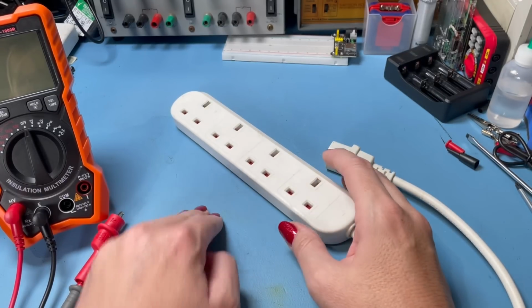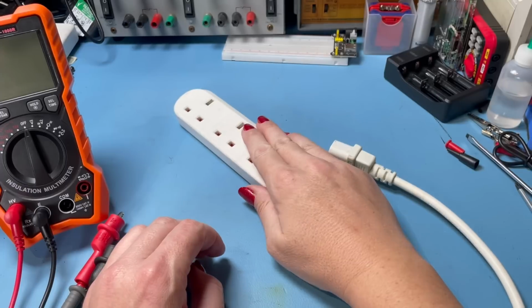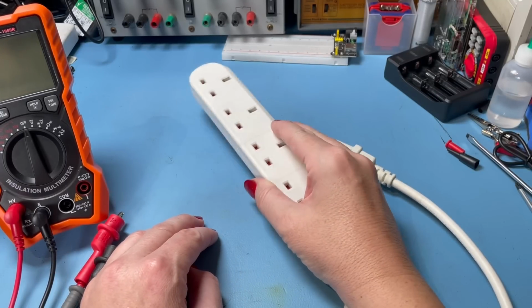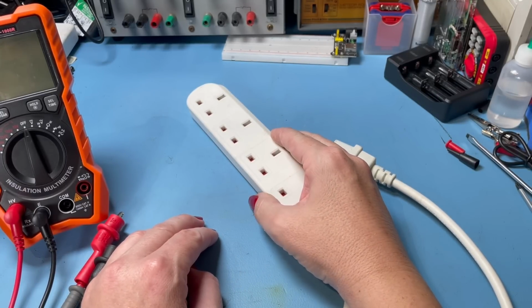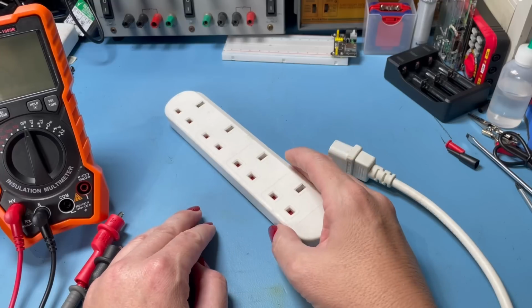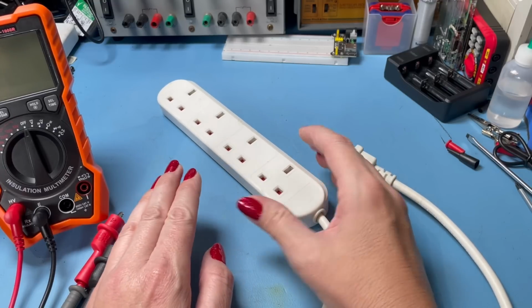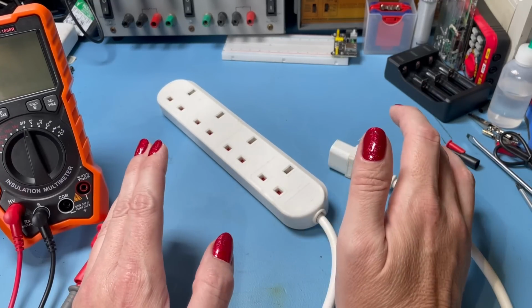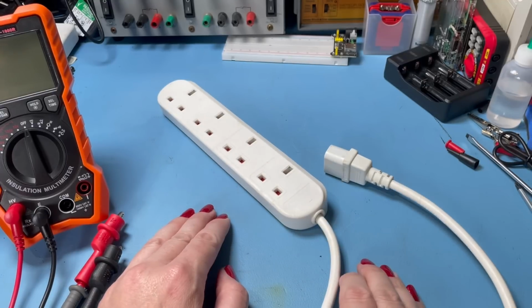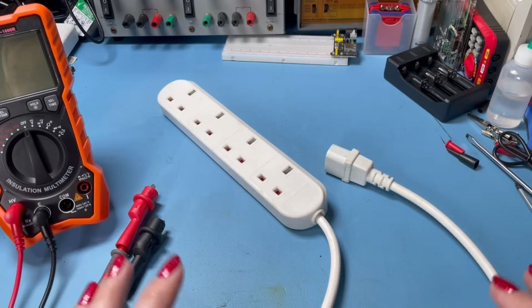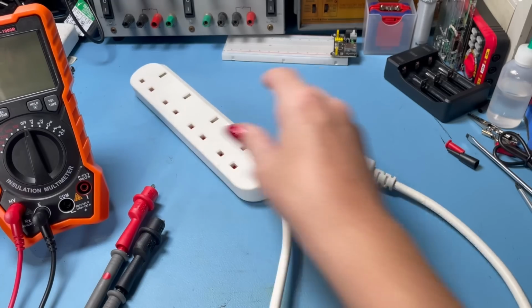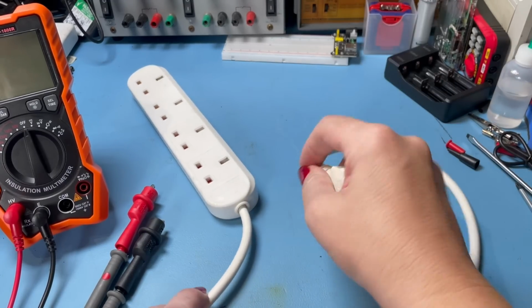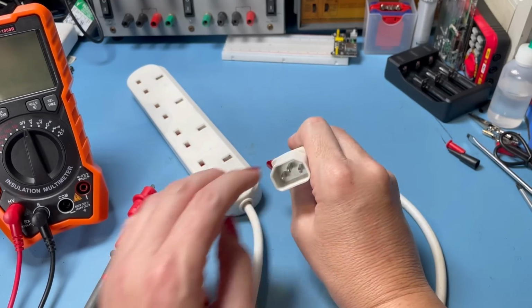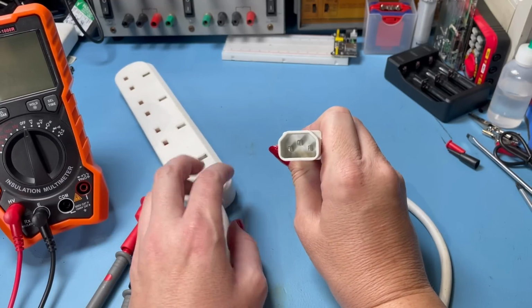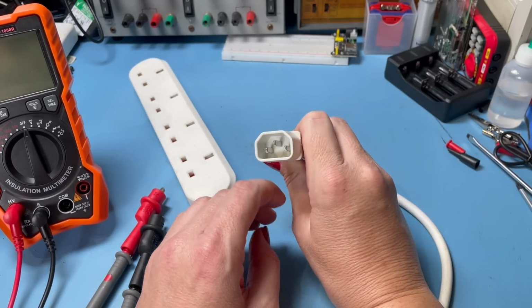But there's a diminishing return for these test voltages. There is no point putting 1000 volts through this, because if you've tested it to 500 volts, that's fine. But if you're testing something like 3-phase, big motors, armoured cables, that sort of stuff, you want to be using 1000 volts for that, because you want to be above the insulation rating. So with my PAT tester, obviously I have a device that this plugs into, and it tests all the pins for me. With this, we're going to do it a little bit differently, in the same way that you would with a fixed wiring installation.